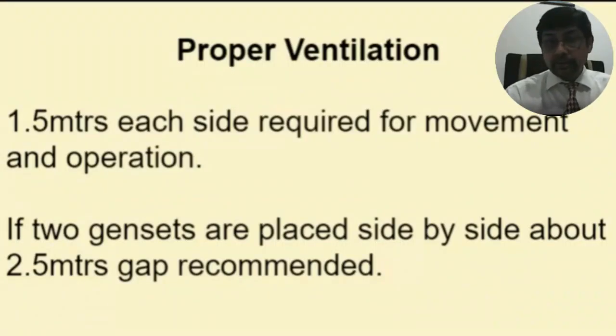And if two gensets, that is the parallel operation or the synchronizing, if two generators are placed side by side together, then we recommend about 2.5 meters, because the thermal heat and the heat dissipation of the generator is such that it should not be overlapping the other generator. The generator is basically driven by the ambient temperature also. If the ambient temperature is high, then probably the efficiency of the generator is going to be low. It is similar to a human being. If we work in a temperature of, say, 38 and 40, our efficiency is going to be low. Whereas if we work in an air-conditioned office where the temperature is maintained at 20 to 22, the efficiency is going to go high. So this is how the proper spacing of the generator will ensure a better efficiency of the genset.